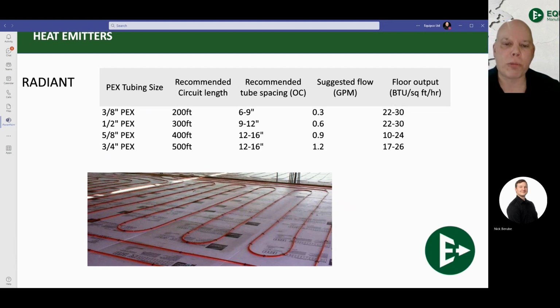There are so many variables on the heat output of radiant systems that all I can give you as far as this training presentation is concerned is ranges. I can give you estimates. So what I'll tell you is this. You are looking at a system that will give you approximately, and I'm going to pick on the 1/2 inch PEX tubing here because that's most common, approximately 22 to 30 BTUs output per square foot. So that's what you're going to be looking at. You have a suggested flow of about 0.6 GPM per loop, a max circuit loop of 300 feet.